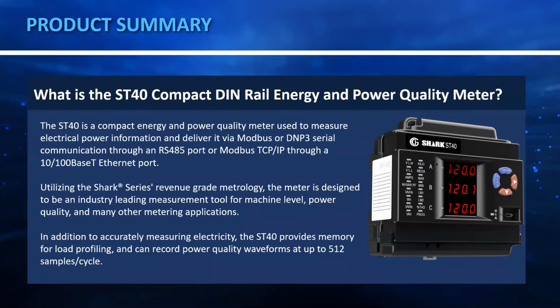So in those cases, you would just snap on this ST40, and then this can deliver all of your data over Modbus, over DNP3. In terms of communication ports, it has both options if you want to collect the data over an RS485 serial port, or it also comes with an Ethernet port. So you can also collect your data over Ethernet. It's utilizing our Shark series' revenue grade metrology, so it is very accurate to 0.2% class accuracy.